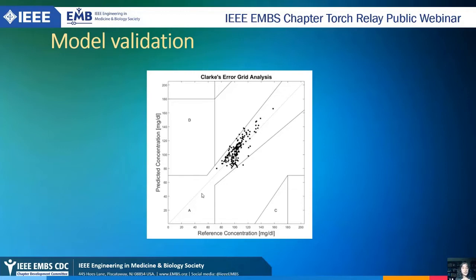In order to validate the obtained results, the Clarke error grid was used. In this grid, it is considered that if the measurements are in the A region they are adequate, in the B region they have more than 20% of error, but it is not a problem. If they are in the C, D, and E regions, the measurement is inadequate. In our model validation, 96% were in the A region and about 4% in the B region.